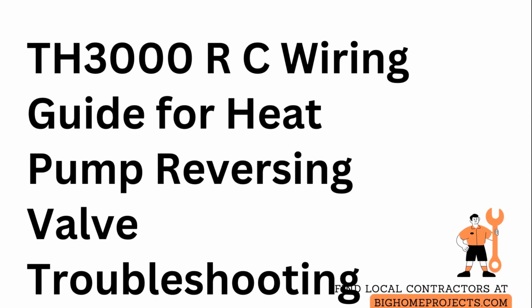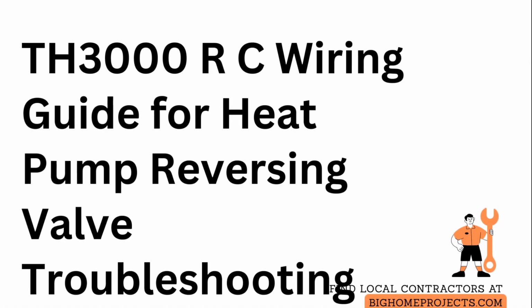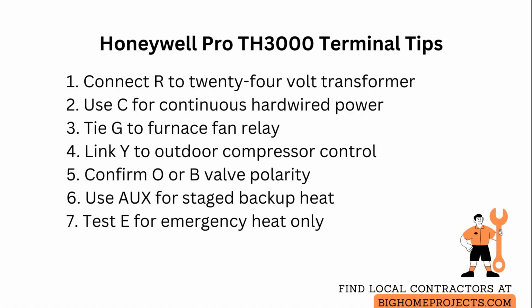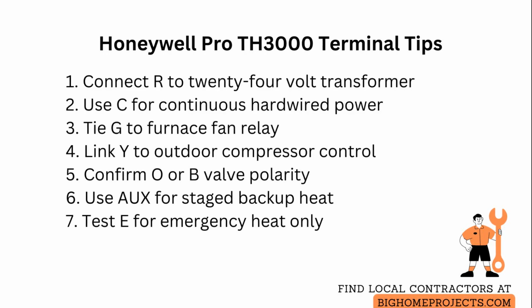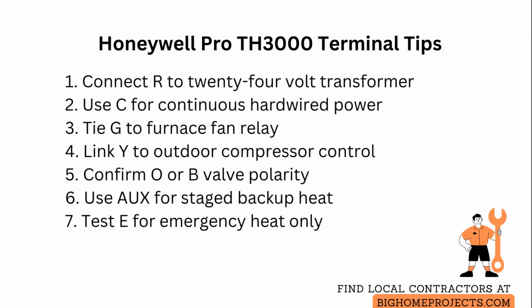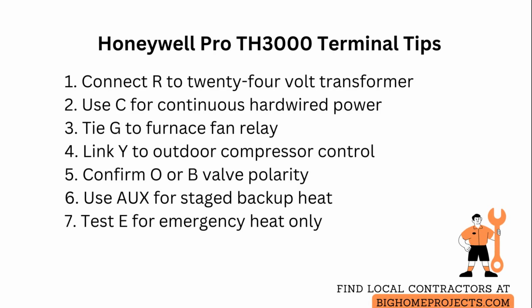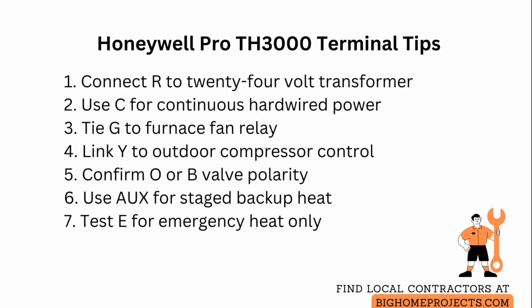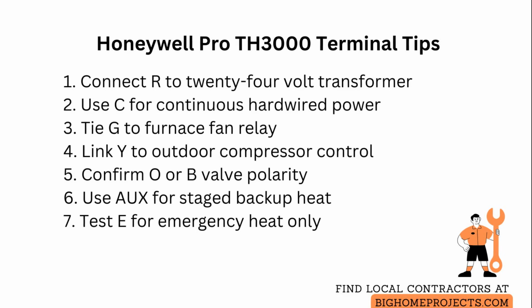What each terminal on a Honeywell Pro TH3000 thermostat represents is critical for wiring and troubleshooting your heating and cooling system correctly. The R terminal supplies 24-volt power from the transformer and is usually the red wire, while the C terminal is the common or blue wire used when the thermostat needs a continuous hardwired power source for features like Wi-Fi or backlighting. The G terminal controls the blower fan and is typically green, so connect it to the furnace or air handler fan relay and verify the fan runs when you manually call for fan.